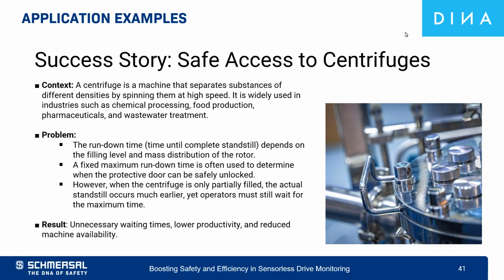And the challenge here is that the rundown time of a centrifuge, the rundown until the complete standstill, highly depends on its filling level and also on the mass distribution of the rotor. And for sure, you can, for example, use a fixed time relay with a fixed rundown time, for example, the maximum rundown time, to control the protective door or to unlock it safely. But let's say when the centrifuge is only partially filled, the rundown time is much shorter, and so the actual standstill occurs much earlier. And then you have waiting time, so the operator must wait for the maximum time, and that's a waste of time, and it lowers the productivity and reduces the machine availability. The standstill monitor, you can avoid this problem.